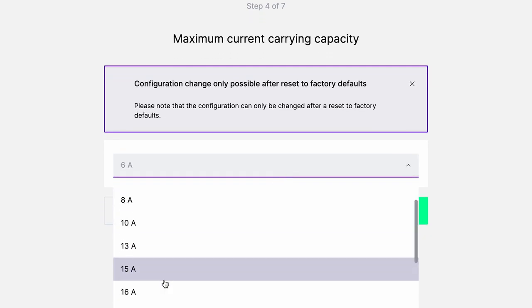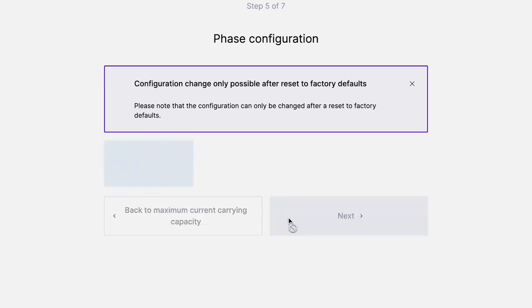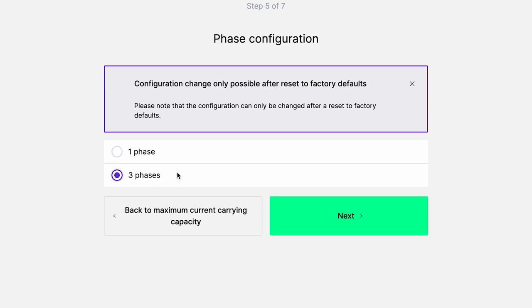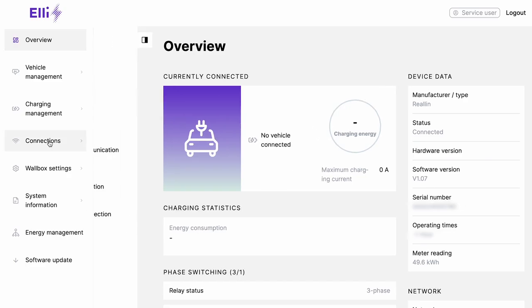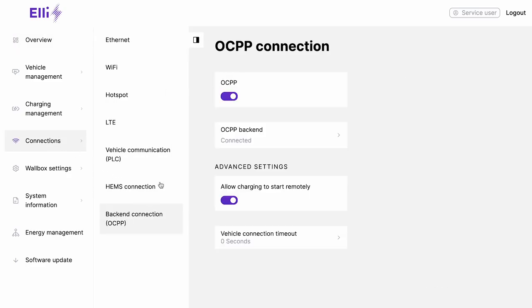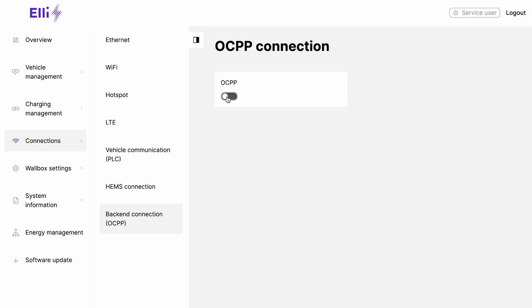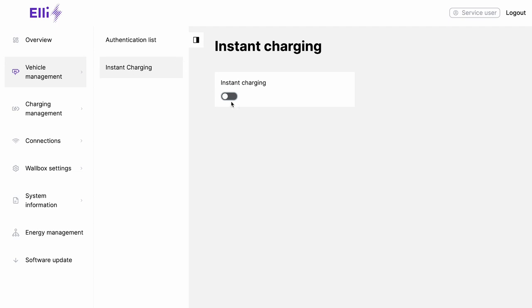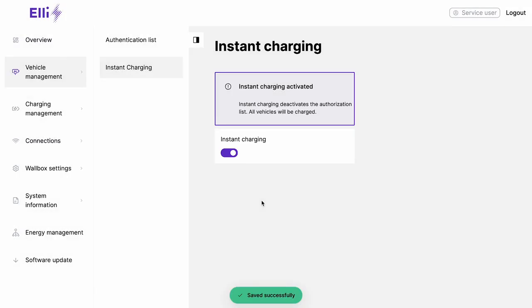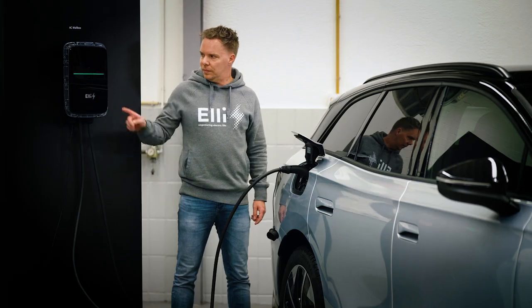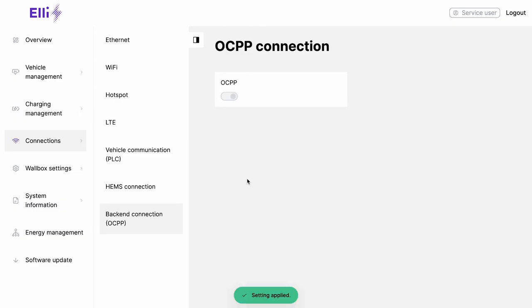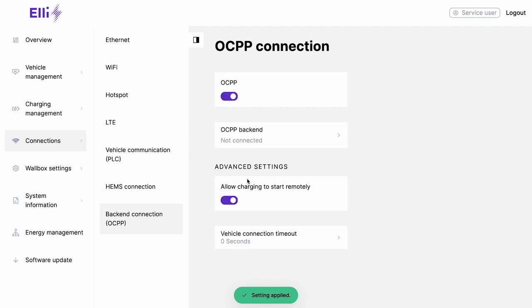Configure the maximum current carrying capacity and the number of phases connected. Note that these settings can only be changed after a factory reset. After the initial configuration, disable the OCPP option in the browser-based wallbox configuration and enable instant charging. Test the charging function. Enable OCPP again when the charging check is complete.